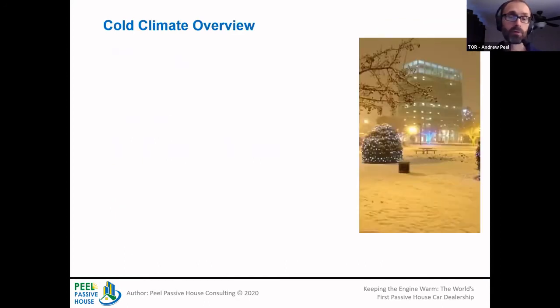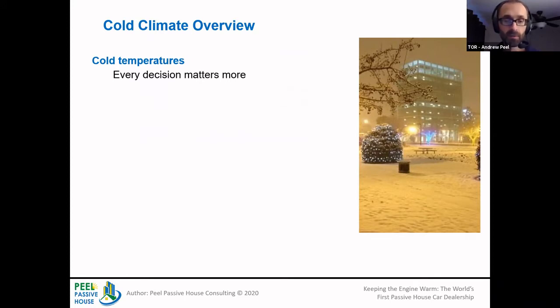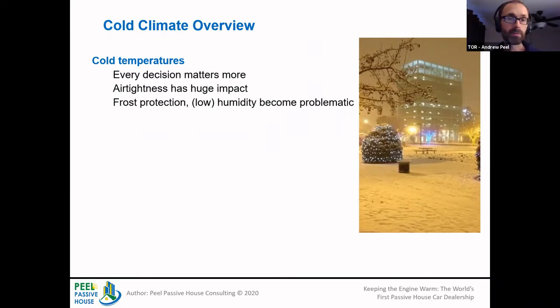A little bit of overview for those who haven't worked in cold climates before. The cold temperatures really have a big impact on the design decisions. Every little decision can actually matter in terms of the performance of the building. We see that air tightness has a noticeably larger impact. Aspects of equipment start to show up that are challenging, such as frost protection. Low humidity can be an issue. And also these design temperatures influence the actual functionality of equipment, where some equipment just won't operate at such low temperatures.